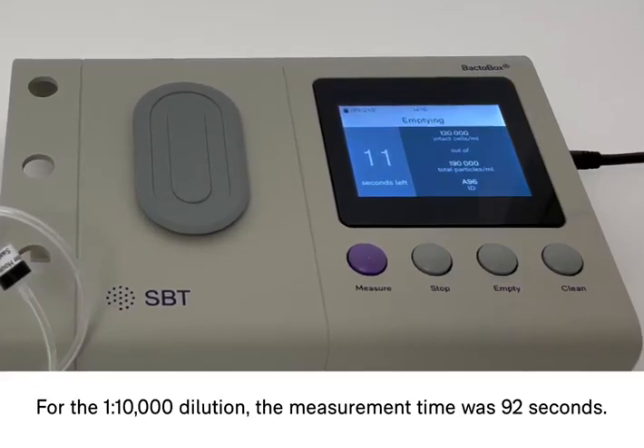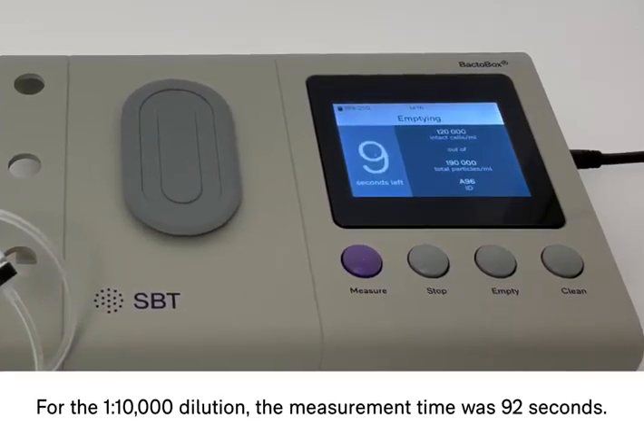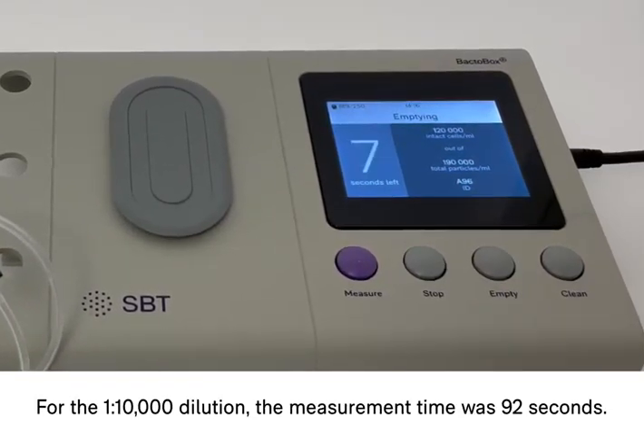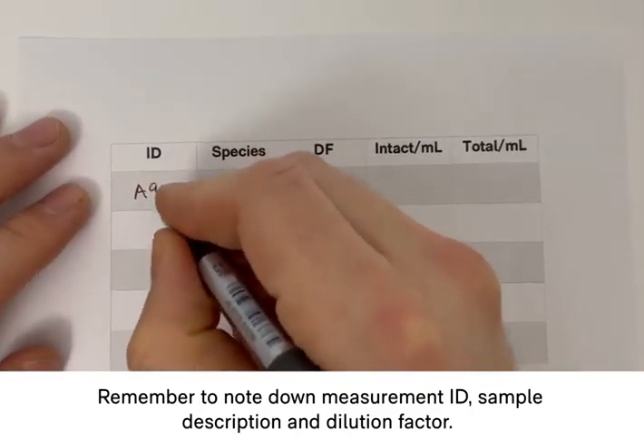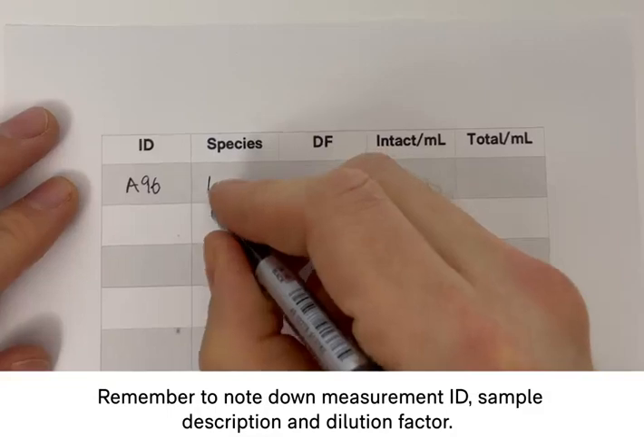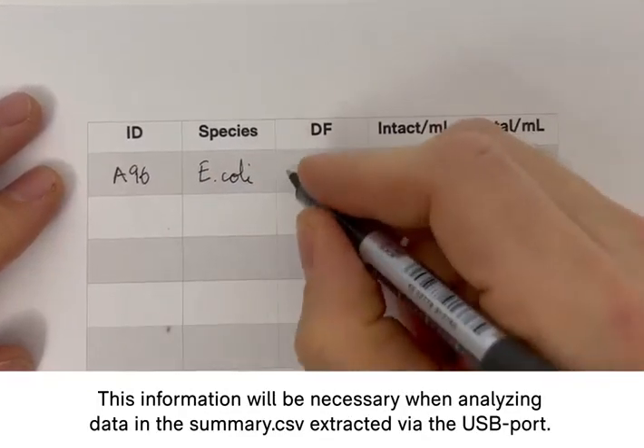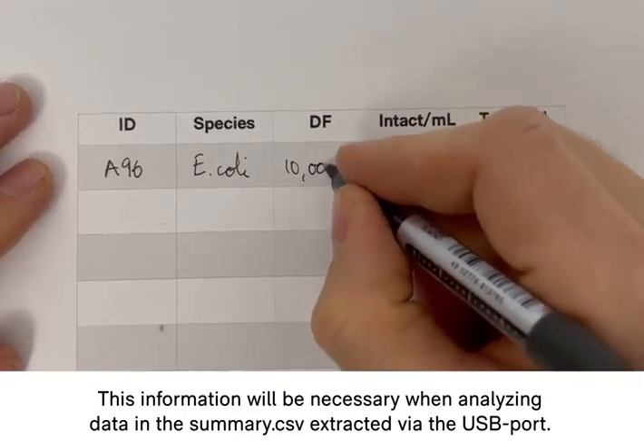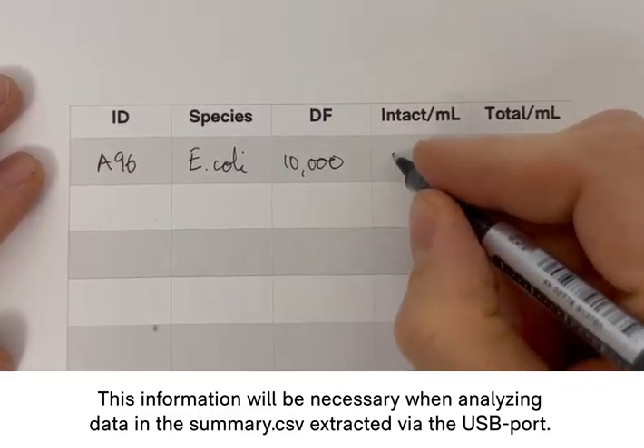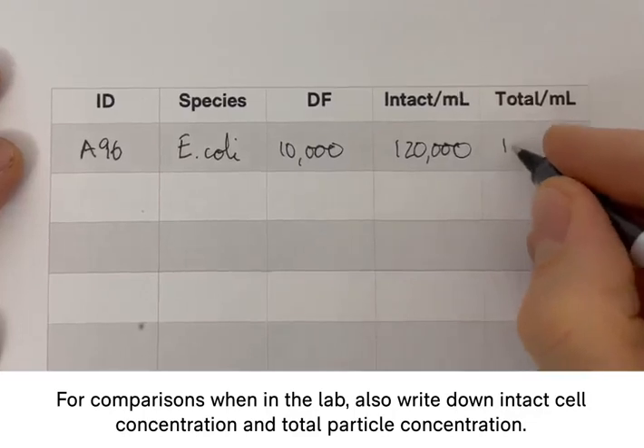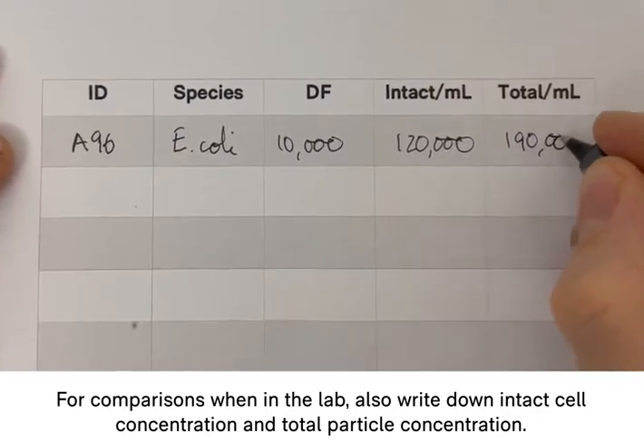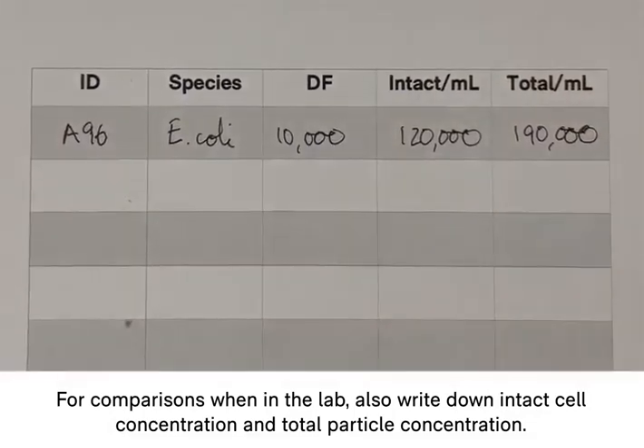For the 1 to 10,000 dilution, the measurement time was 92 seconds. Remember to note down at least the measurement ID, dilution factor and sample description. You'll need this information later when analyzing data in the summary.csv file extracted via the USB port. If you want to do comparisons when in the lab, it's also quite convenient to note down the intact cell concentration and total particle concentration.